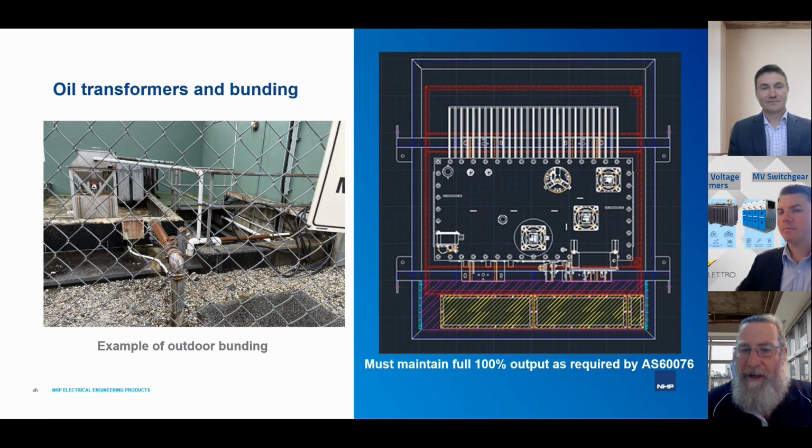they don't have an issue with respect to oil getting into the environment, or, as I said, esters in this case, because the transformer is actually being installed in a national park, so it has a lot of waterways. So it's very environmentally sensitive, and this is the solution that the customer has decided on compared to the photo we see on the left-hand side.